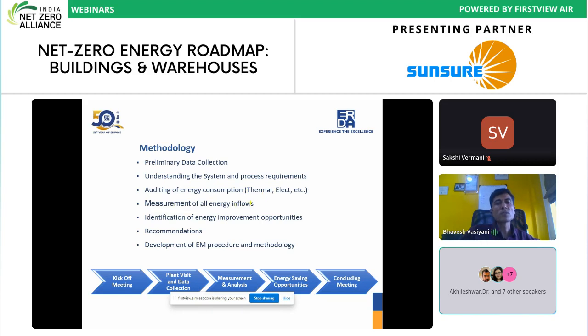Then measurement of those energy inflows and outflows should be done. It can be instantaneous, or in the case of buildings or warehouses, now they are going for IoT also. They are continuously installing BMS, so they can monitor that data continuously. But we have observed that a lot of data is coming to their desk, even though they have installed this online energy management system. The utilization of that data should also be done to find out where there is a possibility. On the input side, energy consumption, voltage, current, power factor, kilowatt, harmonics, everything should be measured. And on the output side, the operating temperature in various conditioned rooms should be continuously maintained and measured. What is the occupancy level in various areas. All these parameters will give the possibilities where energy can be saved.